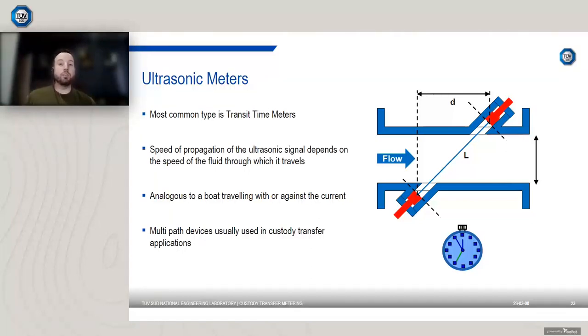If a boat's traveling with the current, it's going to travel faster than against the current. And by comparing the travel time of the ultrasound going with and against the flow, you can determine the velocity of the fluid because it's directly proportional to that. Now the image shown here is a single path device, so there's one path being cut across the flow stream. Typically in custody transfer applications, you'd use a multi-path device.